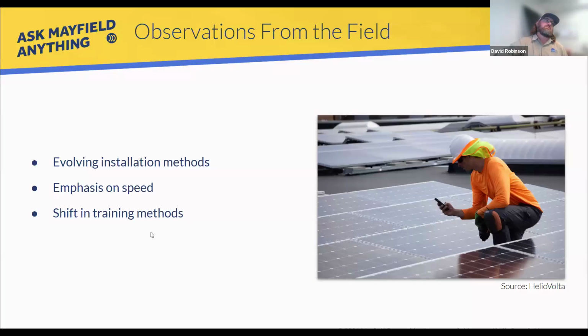The issues we typically see with crosstalk are probably what he's referring to. With rapid shutdown devices specifically, not MLPEs, that signal gets crosstalk, and what happens is it causes the device to open and close rapidly, and that's what typically causes the arc fault. I don't think the signal itself causes a false arc fault reading, we haven't had the chance to diagnose it at that level, but the most common problem we see with rapid shutdown devices is crosstalk, which goes back to installation and design, specking things out and having a really detailed plan set.